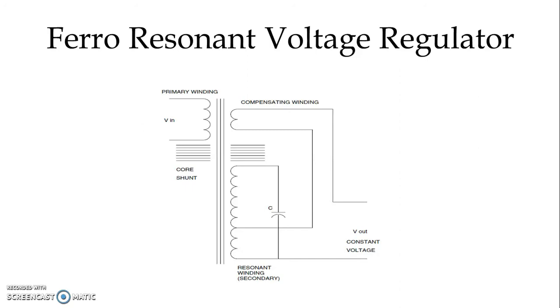They operate on the principle that in a transformer when the secondary magnetic circuit is operating in the saturation region, the secondary winding is decoupled from the primary and therefore is not sensitive to voltage changes in the primary. The secondary winding has a capacitor connected across its terminal that forms a parallel resonance circuit with the inductance of the secondary winding. Large magnetic fields are created in the magnetic core surrounding the secondary windings, thereby decoupling the secondary winding from the primary.